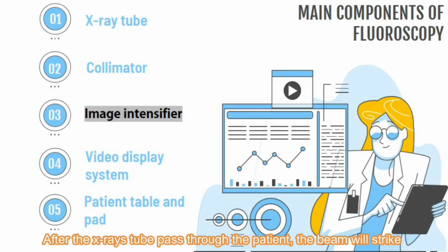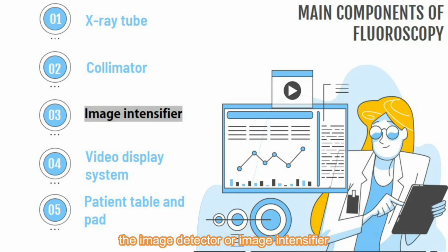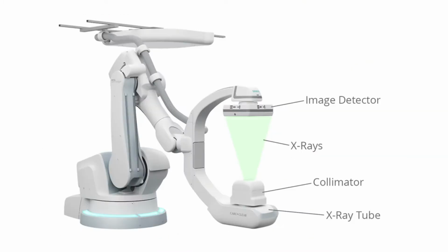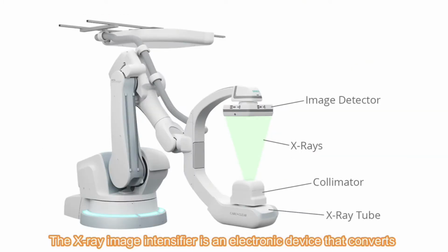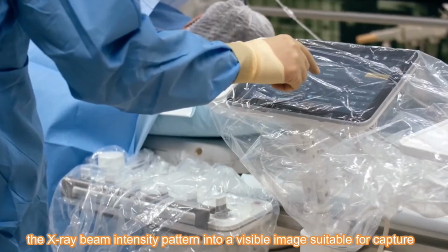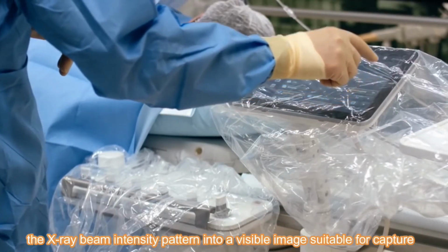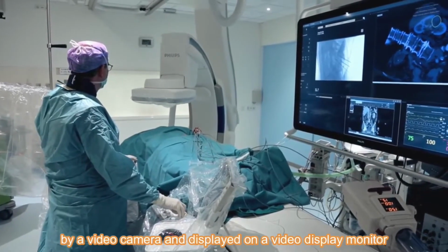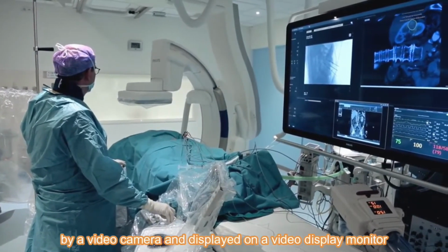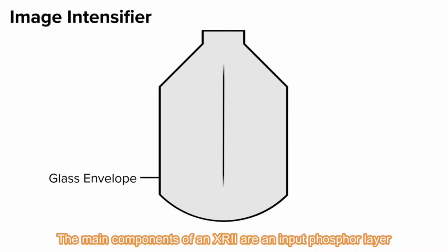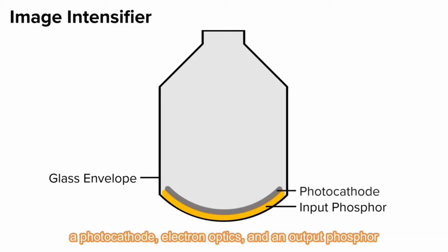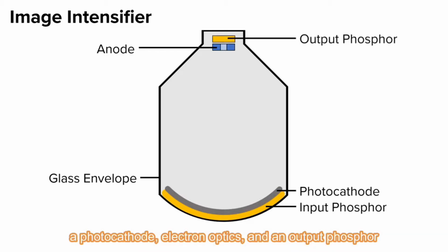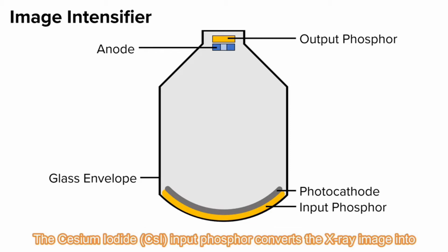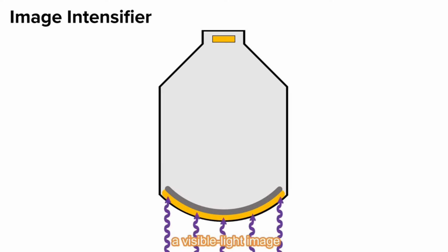After the X-rays pass through the patient, the beam will strike the image detector or image intensifier. The X-ray image intensifier is an electronic device that converts the X-ray beam intensity pattern into a visible image suitable for capture by a video camera and displayed on a video display monitor. The main components of an X-ray image intensifier are an input phosphor layer, a photocathode, electron optics, and an output phosphor. The cesium iodide input phosphor converts the X-ray image into a visible light image.